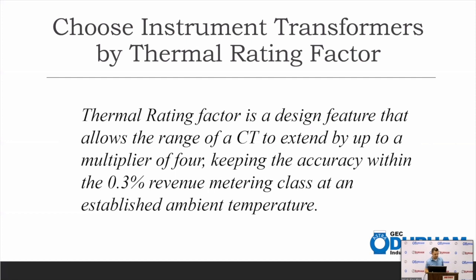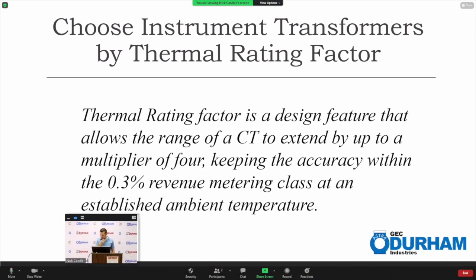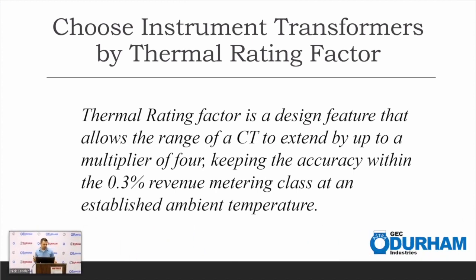Nick, for solar rated sites that are instrument transformer rated, do you recommend a higher accuracy class than the 0.3s? Yeah, good question. That comes up quite a bit. Yeah, unequivocally, yes. As you saw on that transformer, the parallelogram is a much tighter confines, and the manufacturers are forced into a much more accurate transformer, and they do go in most cases way down on the low end as well. So I wouldn't say it's the holy grail, but in some sense you do get to have your cake and eat it too with a high accuracy transformer.